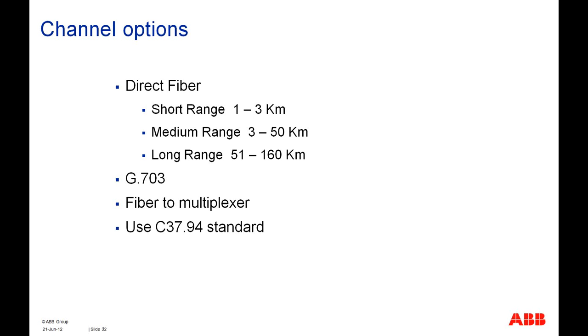Direct fiber can be used for short range, 1 to 3 kilometers, and we can use medium range direct fiber with a different requirement from 3 to 50 kilometers, and then long range. And we can use G703 and MUX also for the communication between the line and relays.